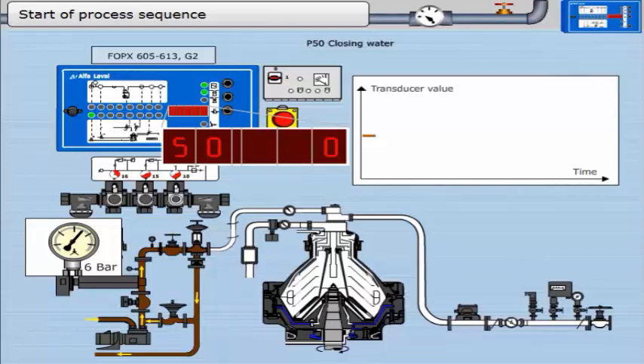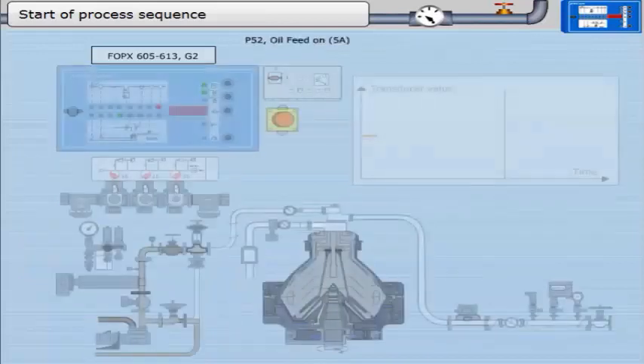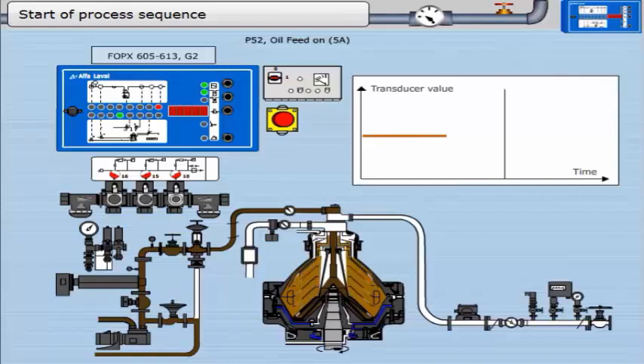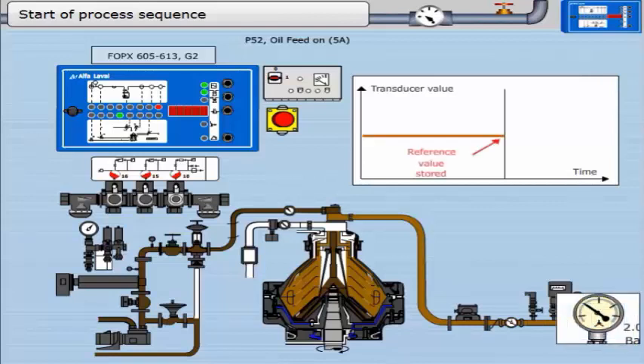The oil is still recirculating around the heater. Next, the oil feed valve changes position and oil is fed to the bowl. This is a stabilizing period for the transducer. The bowl fills with oil and cleaned oil is discharged by the paring disc. A back pressure is established in the clean oil outlet. The operating back pressure is set by the regulating valve midway between the delivery height pressure — which determines the minimum back pressure — and the pressure required to overflow the bowl. The transducer reference is stored by the EPC 400 at the end of this timer, which runs for 120 seconds.